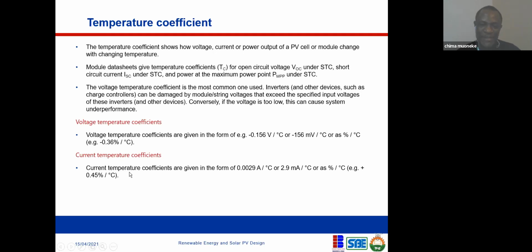Current temperature coefficients are given in the form of, you can see that the numbers are very low, 0.0029 ampere per degree rise. So for every degree rise in temperature, your current can increase by this above the standard test condition. But you can imagine for that degree rise in temperature, your voltage will drop by 0.156 compared to 0.0029 ampere. So the drop in voltage is so significant that this gain is irrelevant. So that's why it is important.